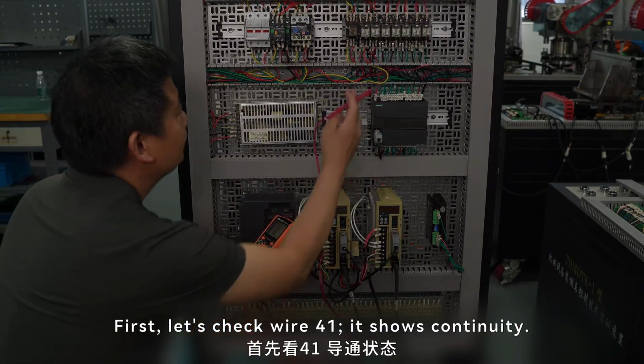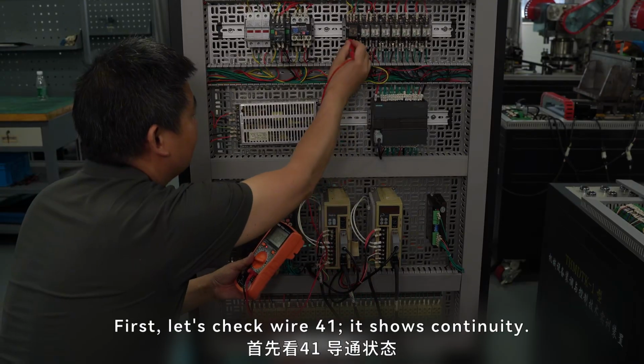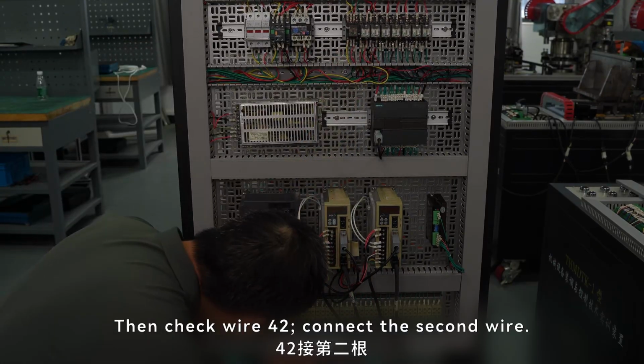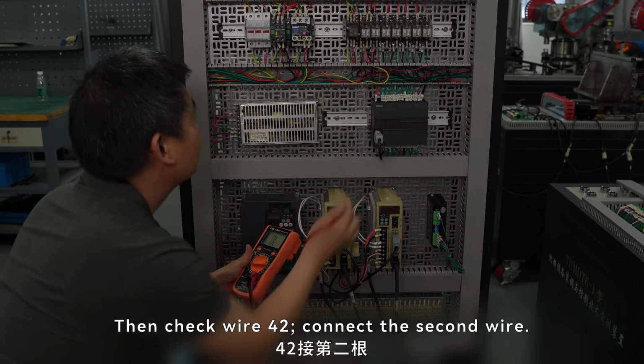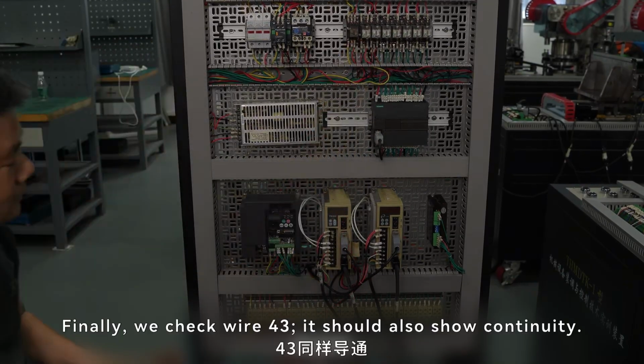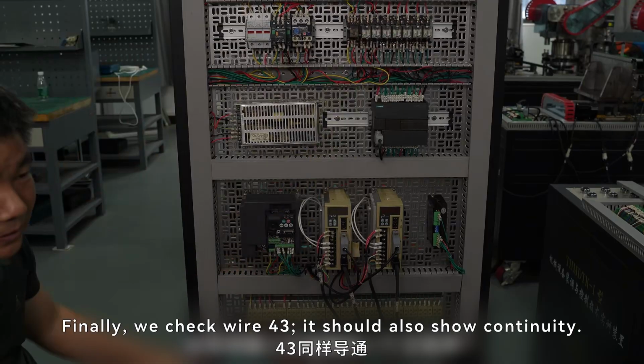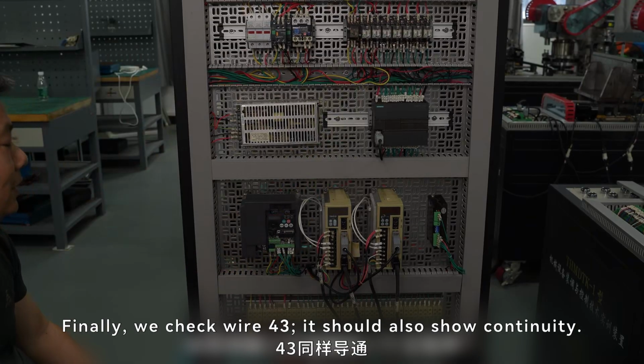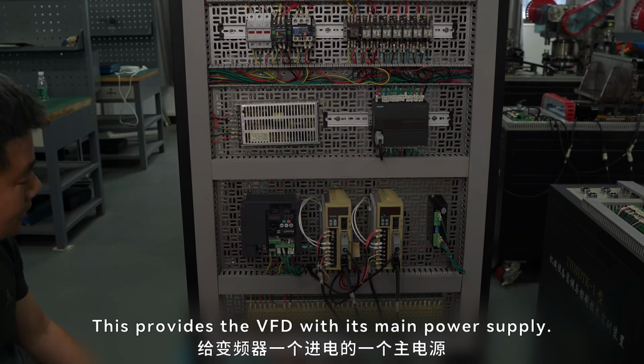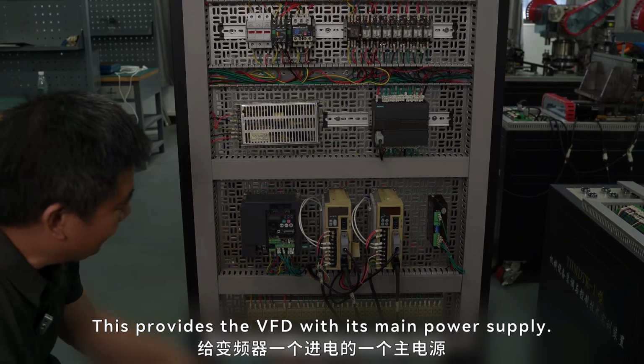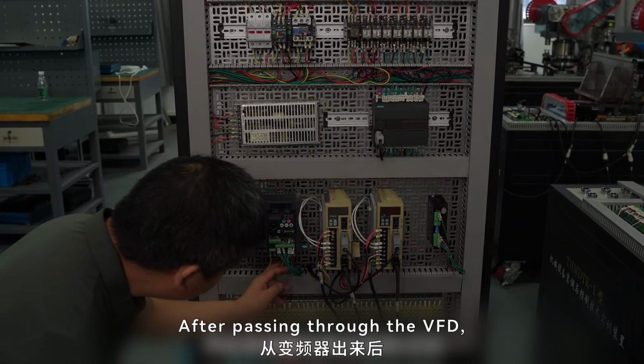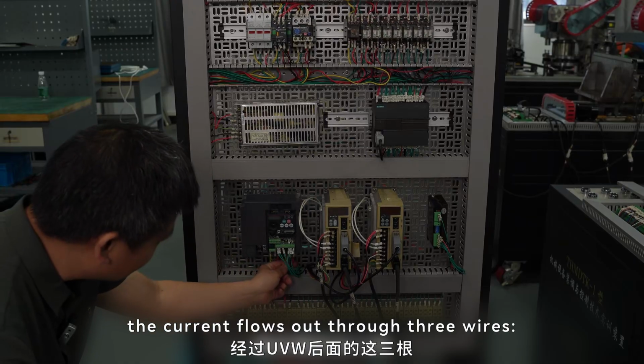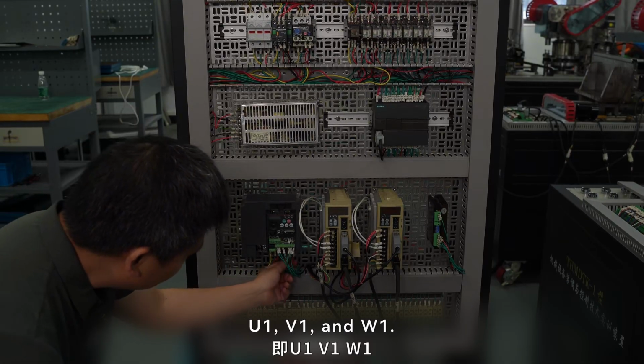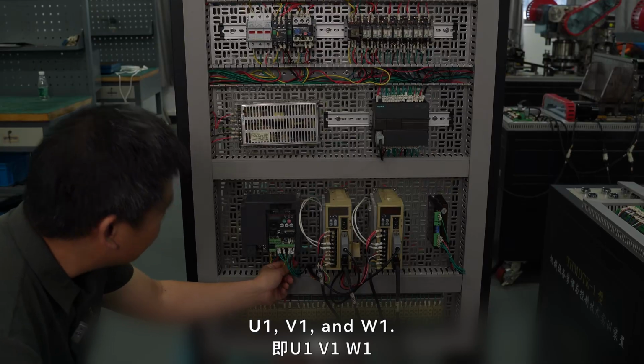First, let's check wire 41. It shows continuity. Then check wire 42. Connect the second wire. Finally, we check wire 43. It should also show continuity. This provides the VFD with its main power supply. After passing through the VFD, the current flows out through 3 wires: U1, V1, and W1.